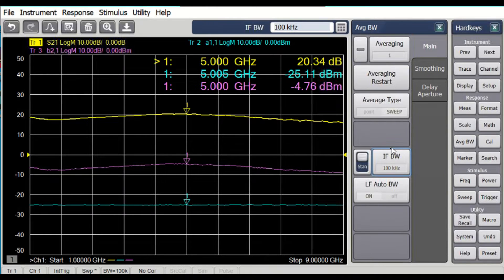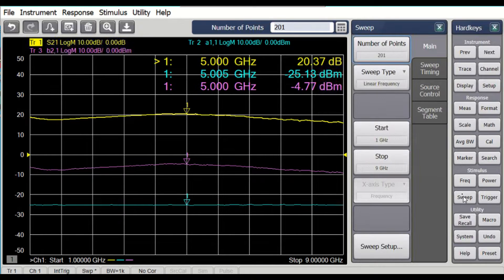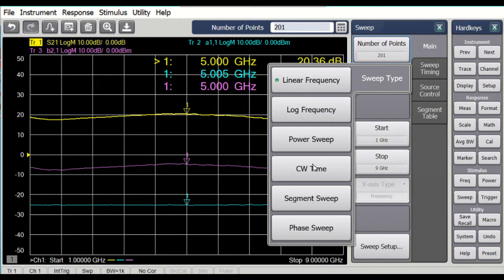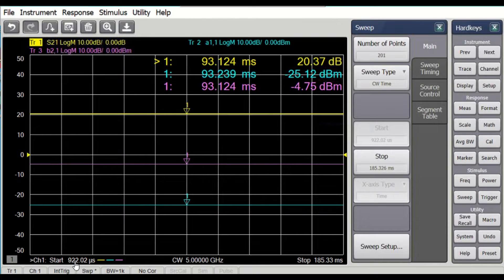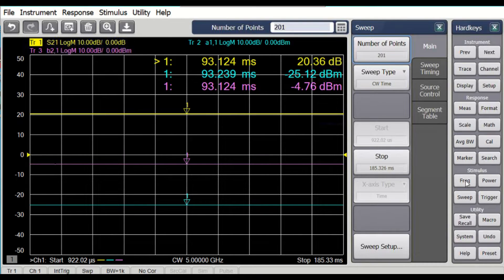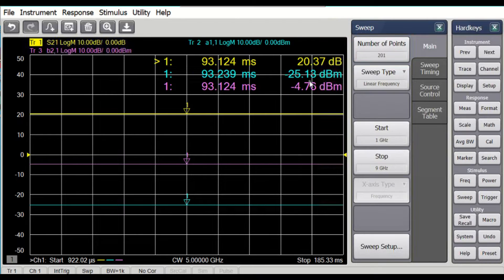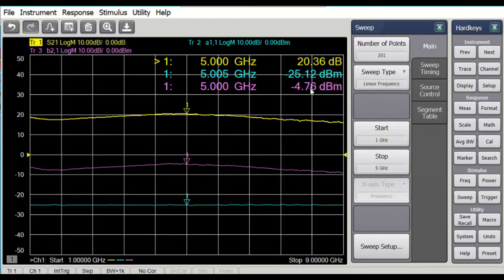Now as I change the IF bandwidth, I want you to notice that the sweep time will change. Let's change it to 1 kilohertz — and we see the sweep slows down. If I go back to the CW time sweep type, now you see the start is 922 microseconds, which is the data acquisition time for a 1 kilohertz bandwidth, and the stop is 185 milliseconds. Going back to the linear sweep, we can see there is less jitter in the measurement. So let's look at what we might do for a pulse measurement.